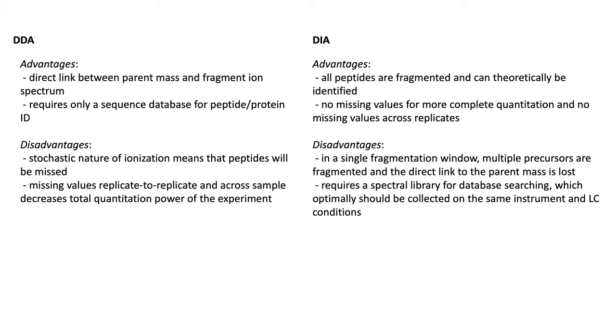With DIA, all peptides are fragmented and can theoretically be analyzed, so there are no missing values and there's more complete quantitation across replicates. However, in a single fragmentation window, multiple precursors are fragmented and the direct link to the parent ion is lost. Therefore, spectral libraries are required for database searching, such that the fragments can be matched to a known library, pulled out, and then continue to be searched. Optimally, these libraries should be collected on the same instrument and using the same LC conditions as the final run, so you still need some DDA experiments for every DIA experiment.